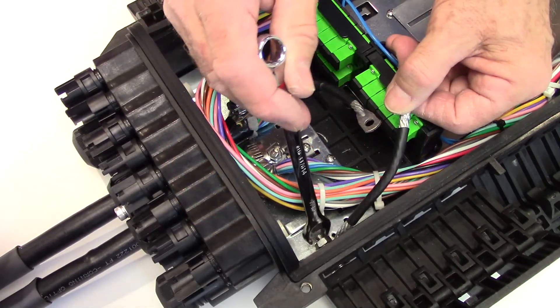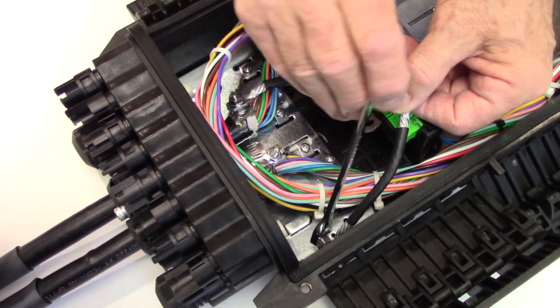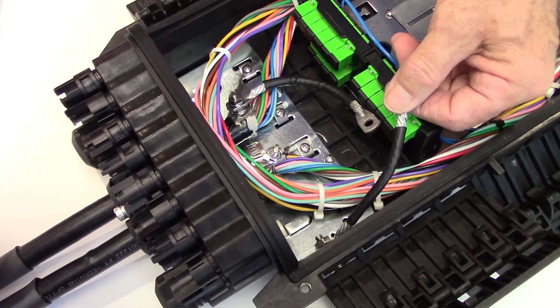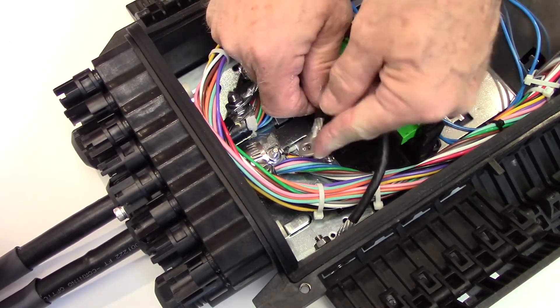When using armored cable, attach a supplied cable bond strap to the ground feed-through and then couple the two straps together at the bond clamp stud.